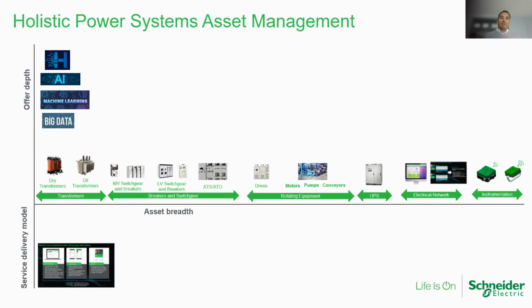We saw this with a particular customer where one breaker was heating up, but not because of a loose connection—it was heating up because of harmonics on the system. The root cause was not the breaker, it was the harmonics. When you combine monitoring of your electrical network with monitoring of your electrical equipment, you can really hone in on what is actually causing the problem—the root cause.